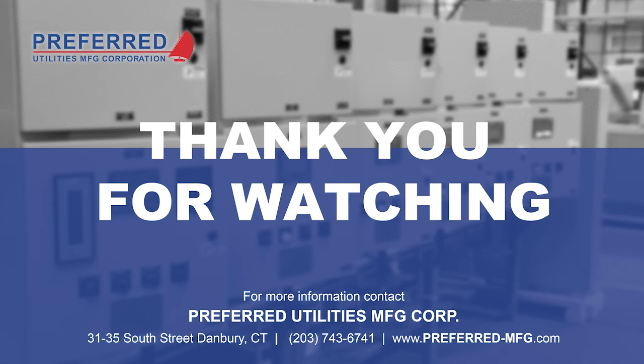We used to package these with a biocide, and then we found that low levels of biocide in your fuel all the time can actually develop biocide resistant bacteria in your tank. And if you get that and the biocide isn't working, then your tank has to be drained and professionally cleaned before you can put fuel back into it. So we don't recommend a biocide anymore, but a fuel stabilizer to reduce the thermal degradation is a good idea.